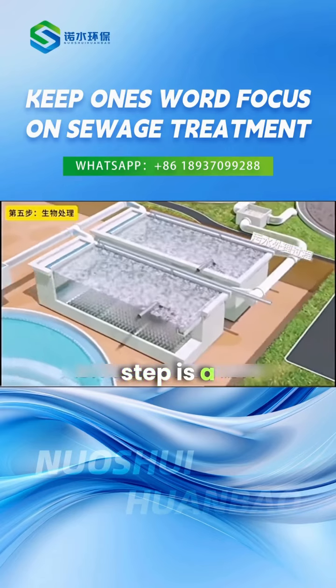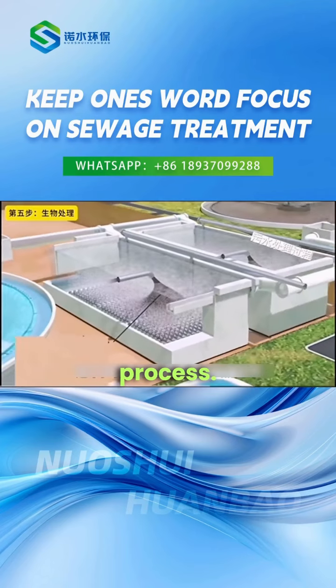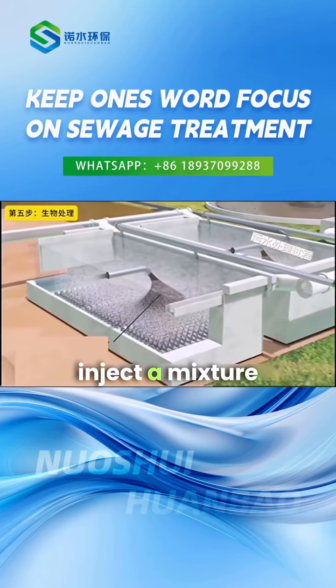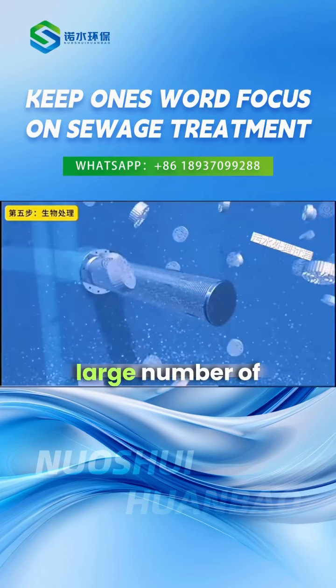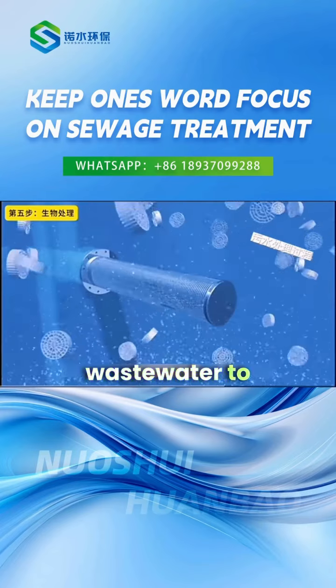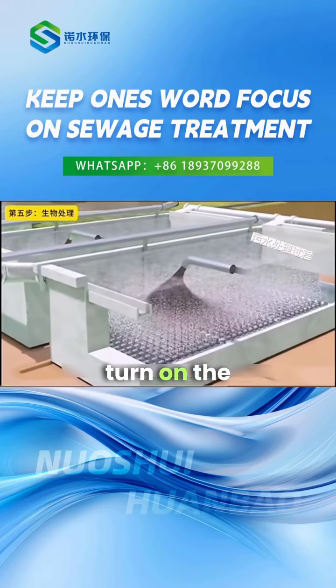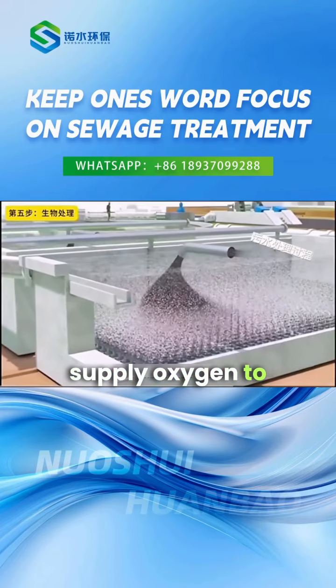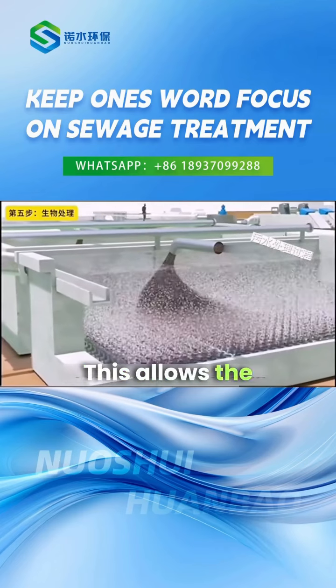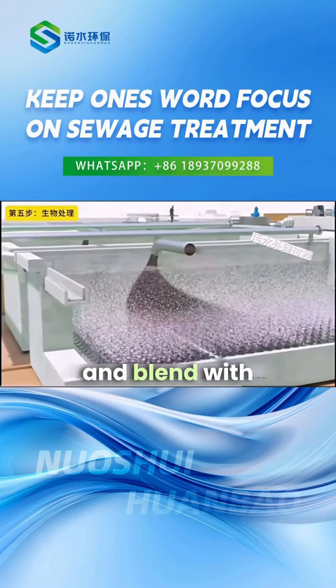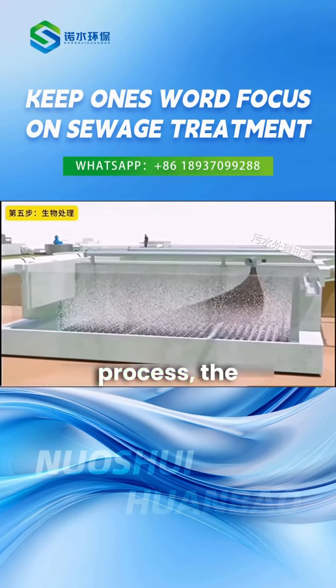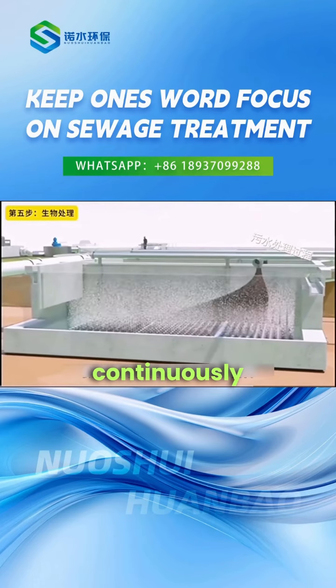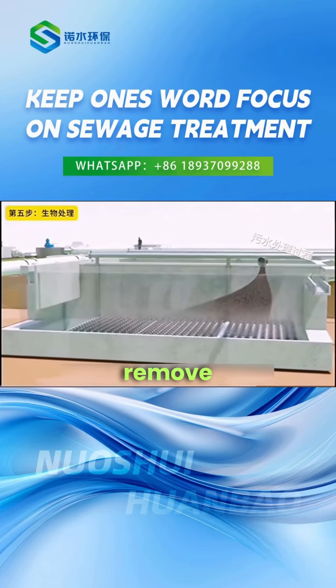Note that this step is a crucial part of the wastewater treatment process. First, workers inject a mixture of activated sludge containing a large number of microorganisms into the wastewater to degrade impurities, and turn on the aeration equipment to supply oxygen to the microorganisms. This allows the organic matter to fully come into contact and blend with the microorganisms. During this process, the microorganisms continuously break down and absorb organic matter to remove impurities.